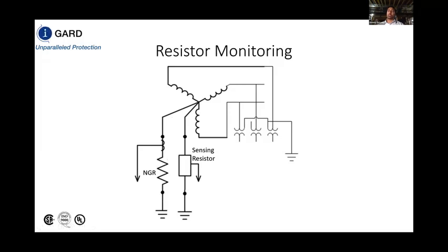So the way that we do that is we use a high frequency AC injection method that takes the path up through the sensing resistor up to the XO point. And because the high frequency AC injection sees the inductance on these 3 phases as a higher impedance than the NGR itself, the majority of our signal takes the path down the NGR and gets confirmed at the relay.